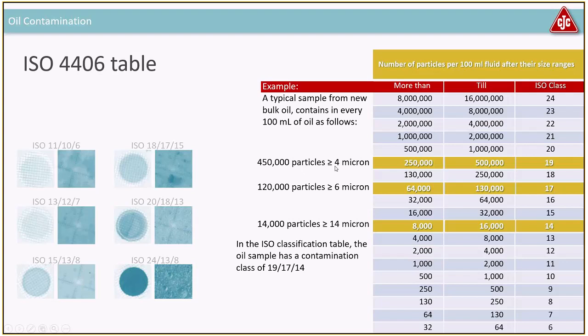As an example using new oil from a drum: 450,000 particles ≥4 microns, 120,000 ≥6 microns, and 14,000 ≥14 microns. Moving these numbers into the ISO 4406 table: 450,000 is between 250,000 and 500,000 — class 19. 120,000 is between 64,000 and 130,000 — class 17. 14,000 is between 8,000 and 16,000 — class 14. So instead of listing all those numbers, I say ISO code 19/17/14, meaning a maximum of half a million particles per 100 mL at ≥4 microns.